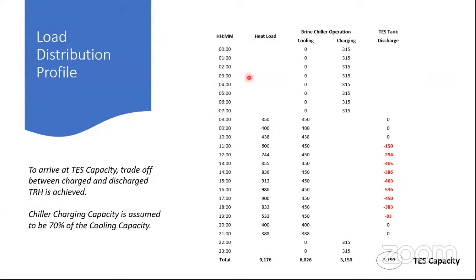So this is a load profile that we have assumed, let's say, to understand the system design. In this load profile, we have hourly load, and we also have a chiller operation, and this is our heat load, and we have assumed the chiller to be of size 450 tons. That's a 450-ton capacity. To arrive at the thermal storage capacity, a trade-off between charge and discharge TRH is achieved.